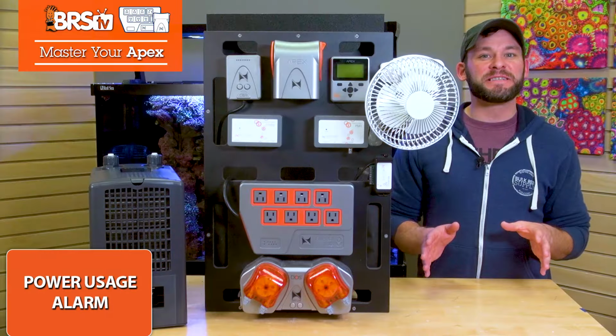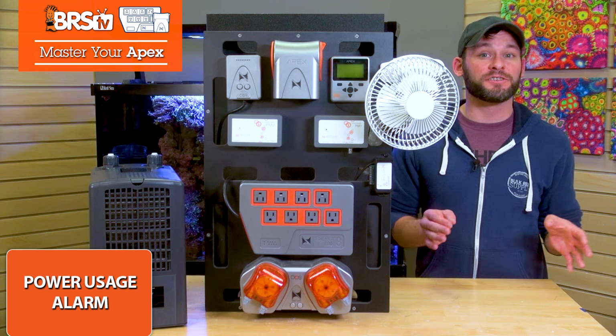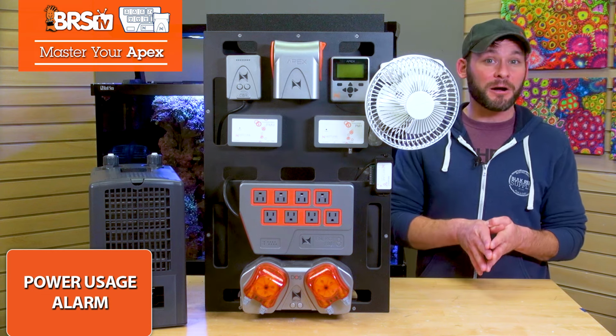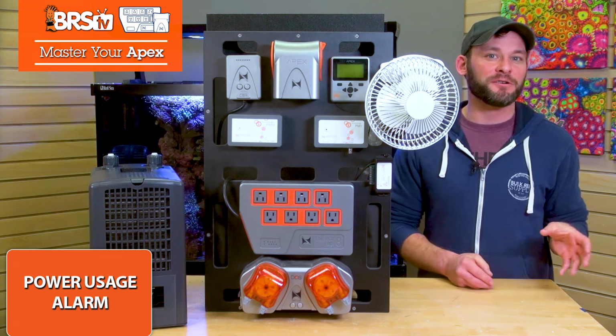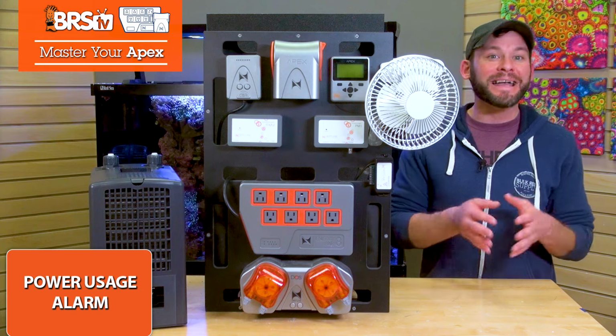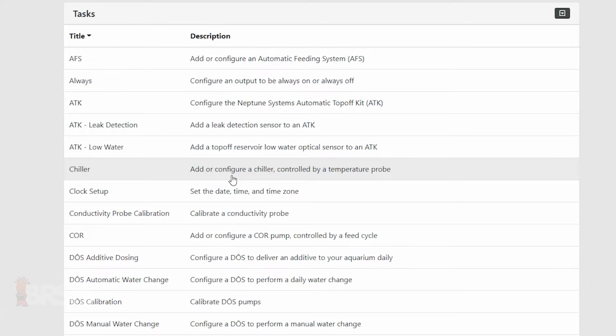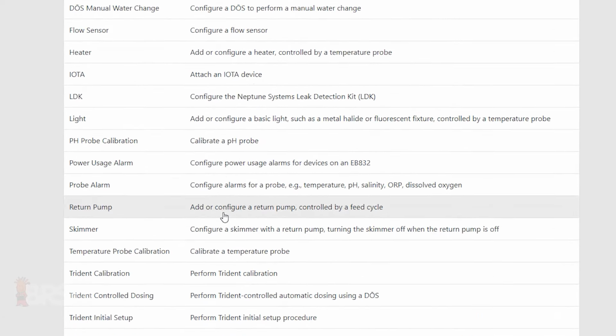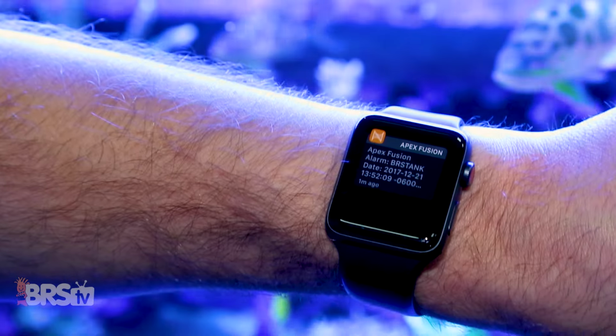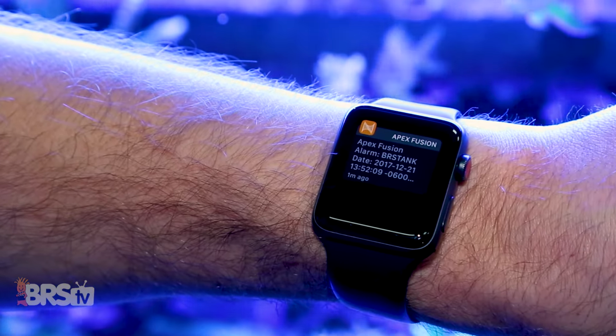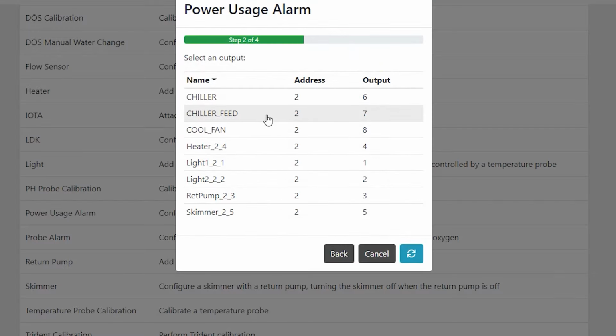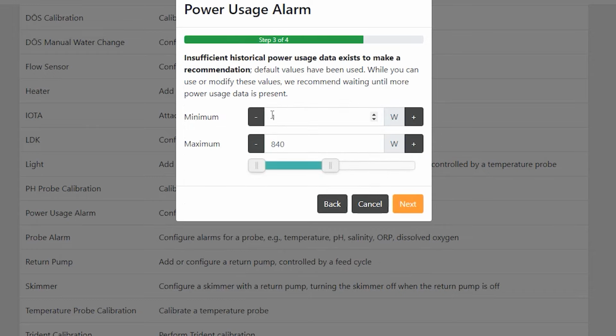Now let's solve those potential chiller issues that I mentioned earlier, starting with your chiller feed pump and knowing the moment that it fails or when it's bogging down and might need some maintenance. We can do that with monitoring the power draw of your feed pump, which will send you an alert when the pump is drawing less than normal wattage or 0 wattage at all by choosing the power usage alarm task function, choosing your chiller feed outlet, setting the min and max power ranges, and pushing send.